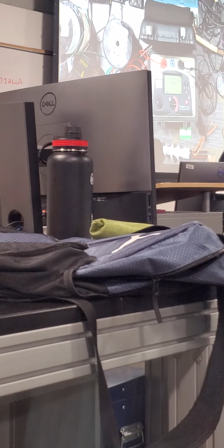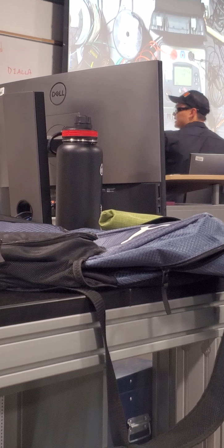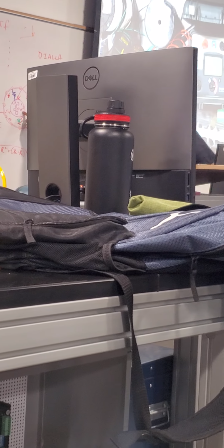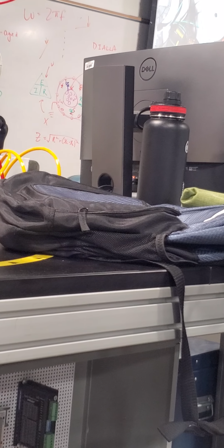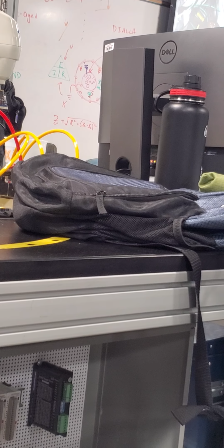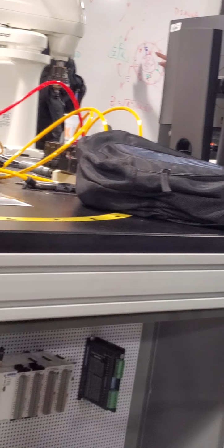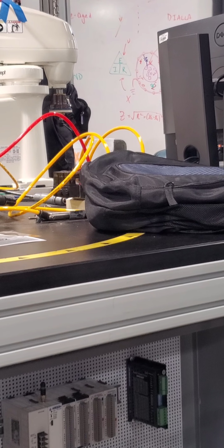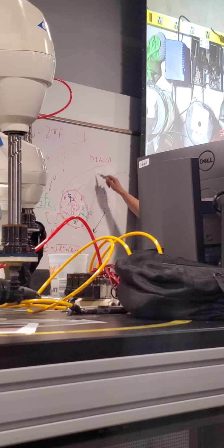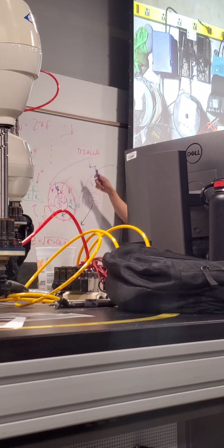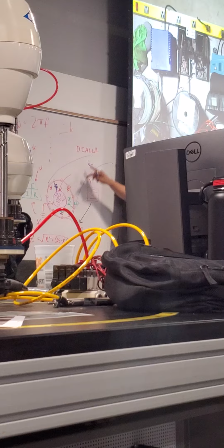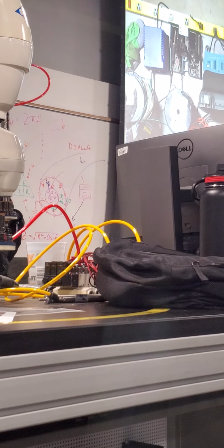All right, so if my test setup looks pretty good, again, we're looking at the main current carrying conductor, which is why I'm on the lug, as well as the outside, right? Meaning we're looking at the bulk insulation here, this resistance. So not only does it look at this cross-sectional area, but for the entire run of the cable, however long this is, right? So if this fault is somewhere here, well, ideally we should be able to detect it because that's kind of your 3D representation.